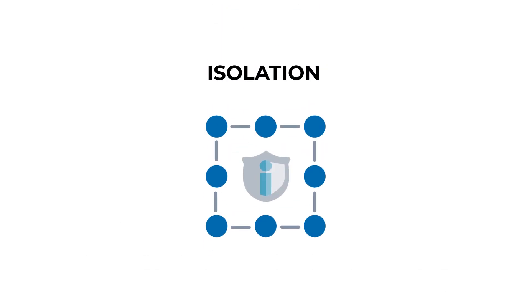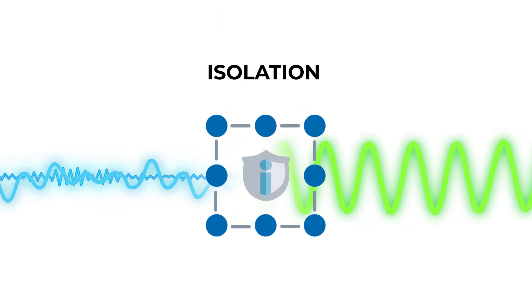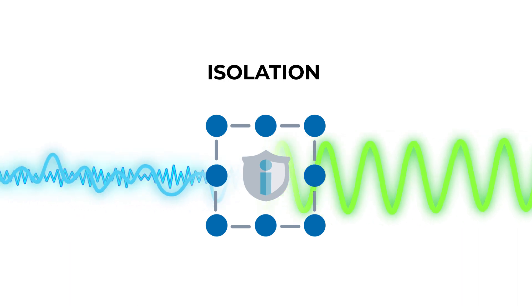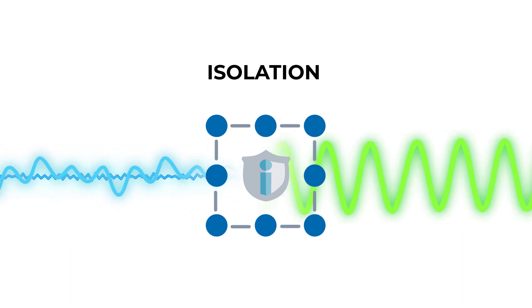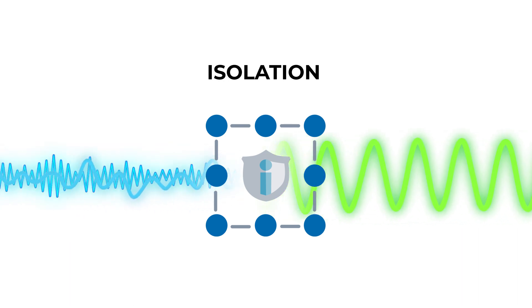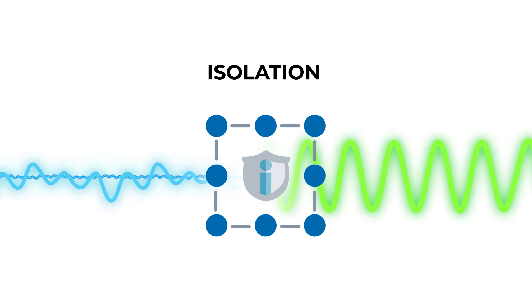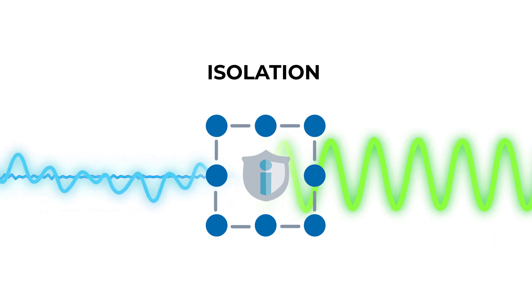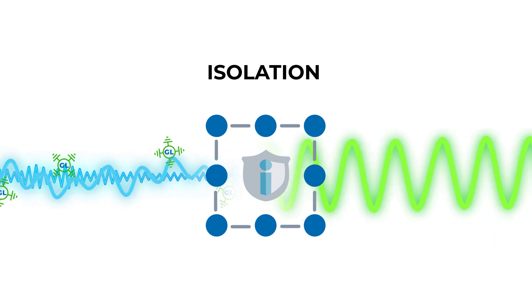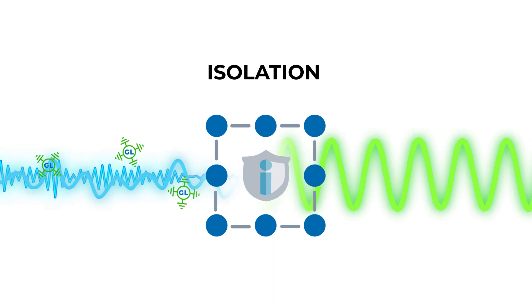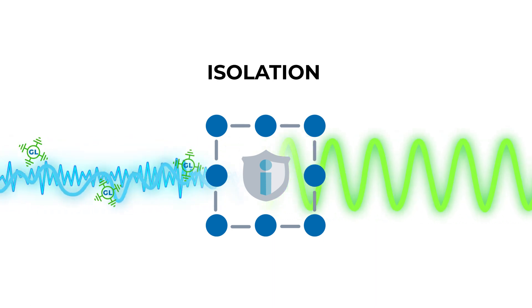Here are some examples of different types of signal conditioning. Isolation helps to protect sensitive equipment from potential hazards that may come through the signal path from the sensor. The isolator can also filter out any unwanted noise along the signal path and eliminate any electrostatic interference caused by ground loops, which can also damage any devices that are connected to the sensor.